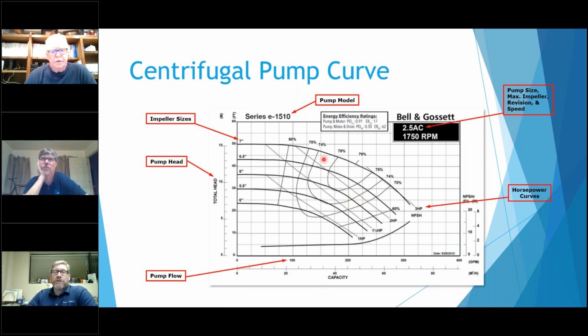Now, one thing I do want to point out: if we were back here and had a 6.5-inch impeller, you can see this 2 horsepower line crosses the 6.5-inch curve. You can actually use a 2 horsepower motor there, but you need to make sure that the flow is roughly under 150 GPM, because the duty point could ride anywhere on this curve. As you approach this horsepower line, at this point right here where the cursor is, you're going to start to overload the motor as you ride on this, what they call riding the pump curve. It depends on what your system pressure or requirements are. You could start to ride over here and actually use more than 2 horsepower, so you're going to start to overload the motor.